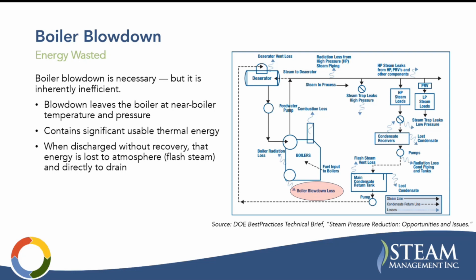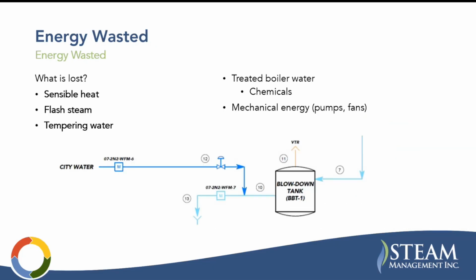You're talking about 2 to 5% in a well-maintained boiler, 2 to 5% of your total steam flow. That's a significant amount of energy. And when it's discharged without recovery, all of that energy is lost. And there's some more losses as well, which we'll go through.